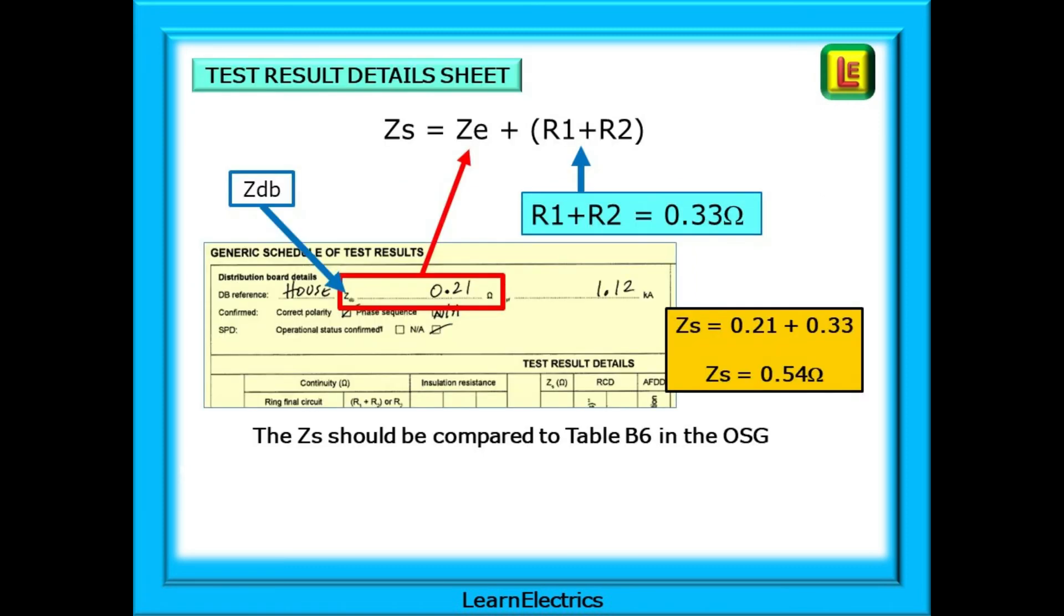If we look at the top of the test results details sheet, we have a line for ZDB. This is the ZE for this consumer unit, 0.21 ohms. There's a reason for it being called ZDB, which is explained in another video. We know that ZS equals ZE plus R1 plus R2, and this formula should be permanently stamped in your memory.